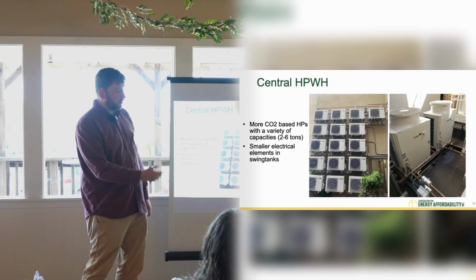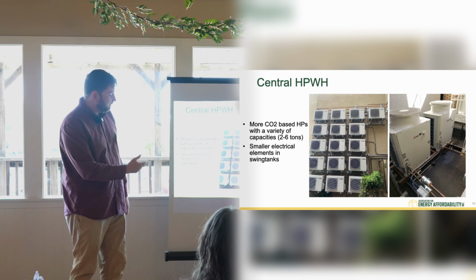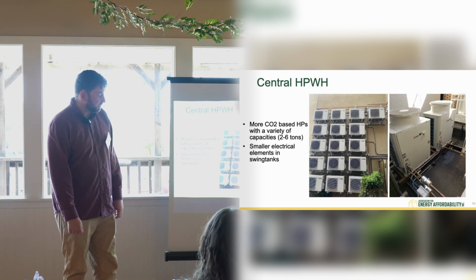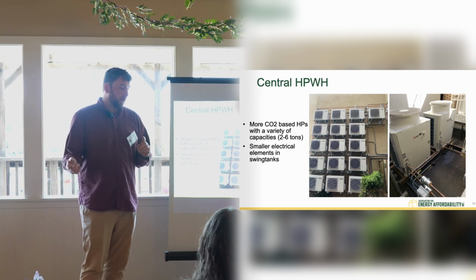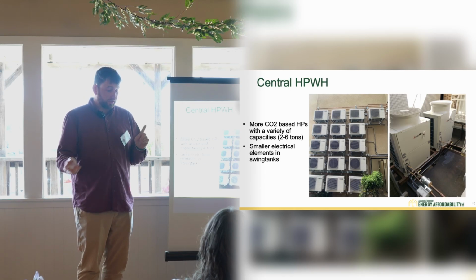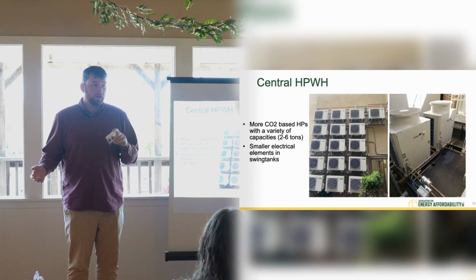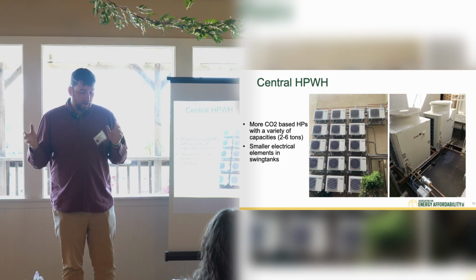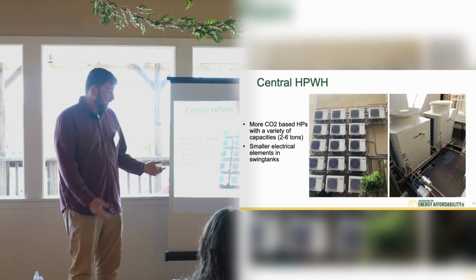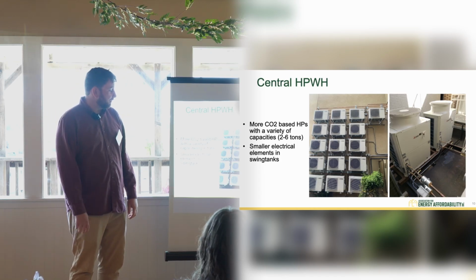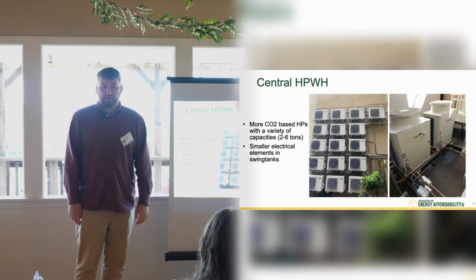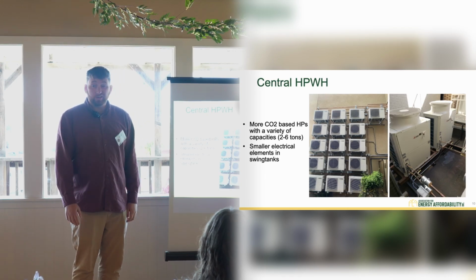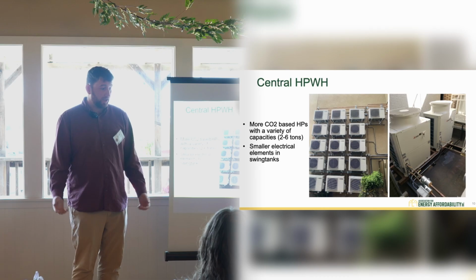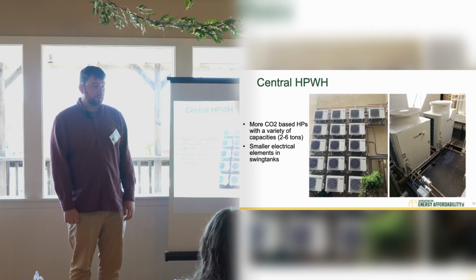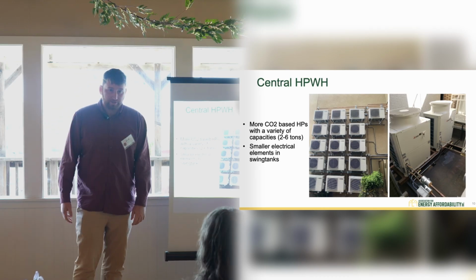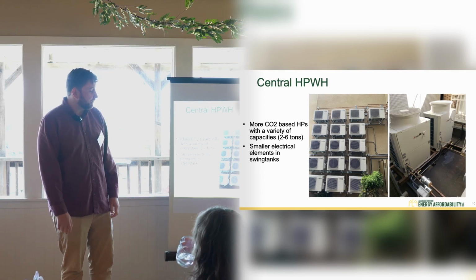In addition to the heat pump water heater itself, we also need variable or smaller electrical elements in swing tanks, as well as residential heat pump water heaters, commercial integrated tank heat pump water heaters. More options for element sizes is going to be critical. I mean, Sanco, the only element that they sell in their swing tank is a 12 kilowatt element. We don't need a 12 kilowatt element in our swing tank for an 8-unit building. That's going to drive demand charges up. So being able to swap out elements to put in 4 kW, 2 kW.